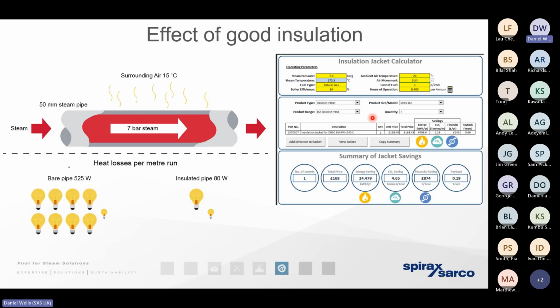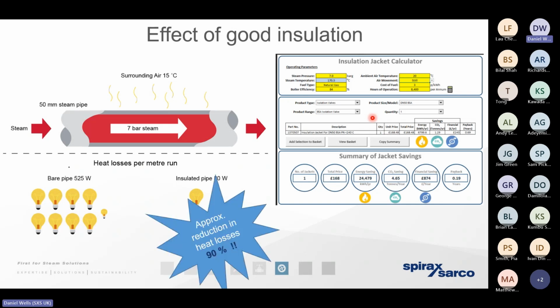The boiler doesn't have to work as hard. But it also means we don't need as many steam traps, so we've reduced the risk of failure. And it also means that by having drier steam with more energy in it, the process is going to take place more efficiently, more rapidly. And we've reduced the risk of that erosion, corrosion, and water hammer from taking place.